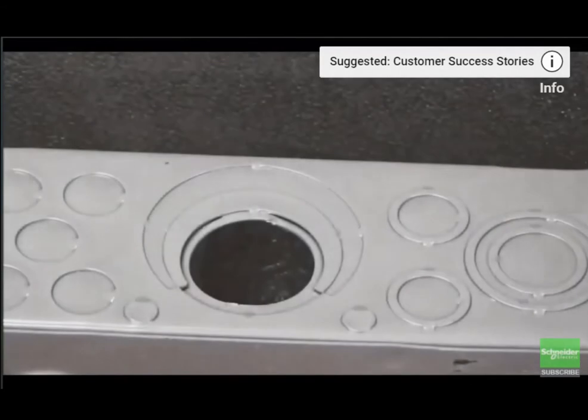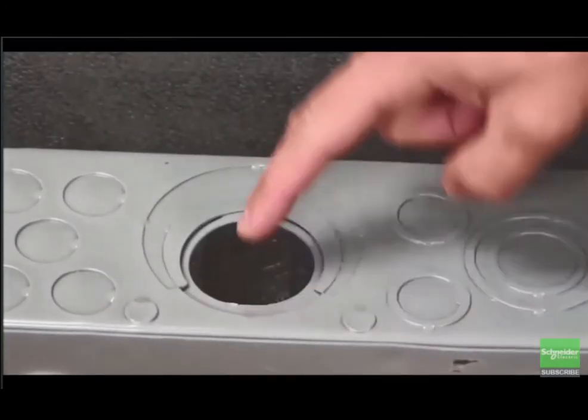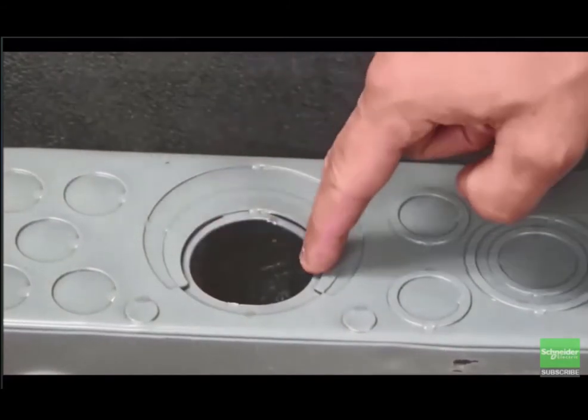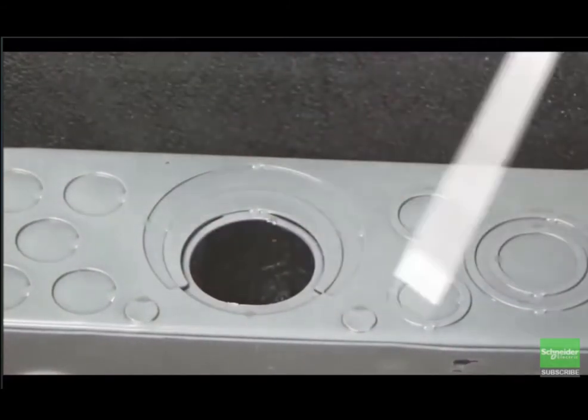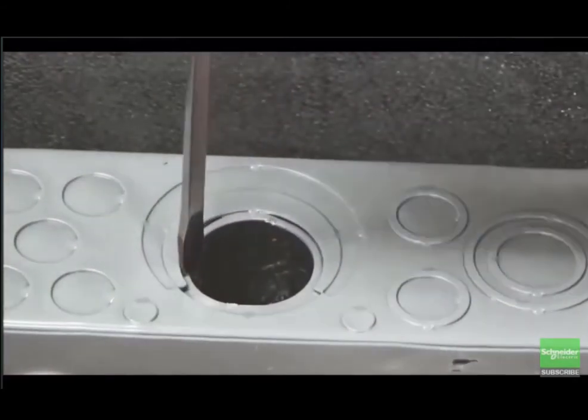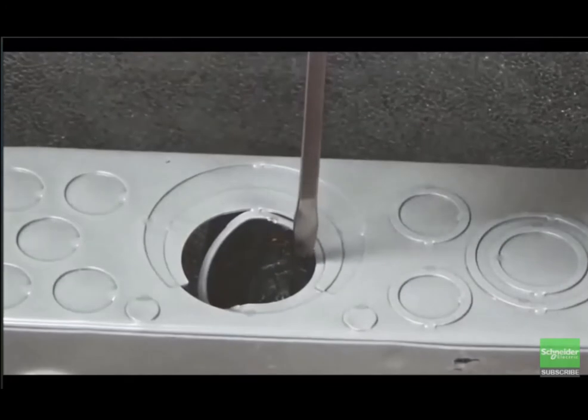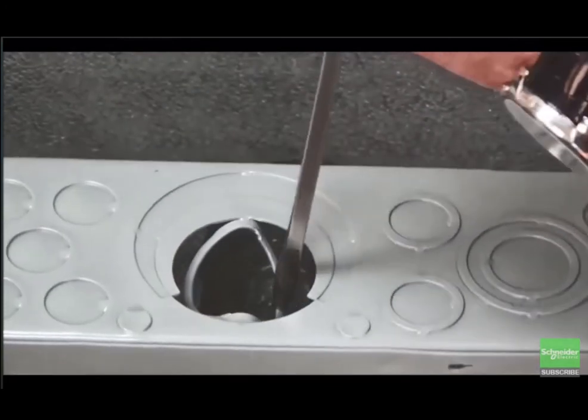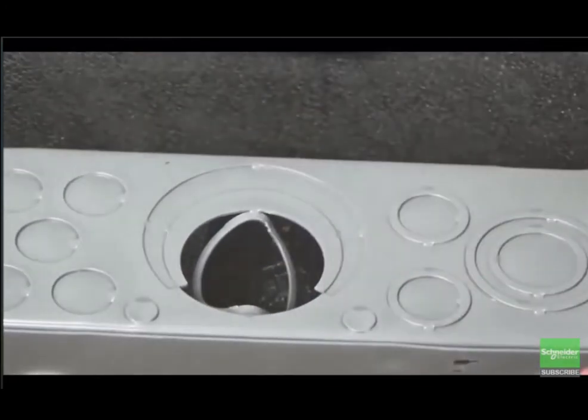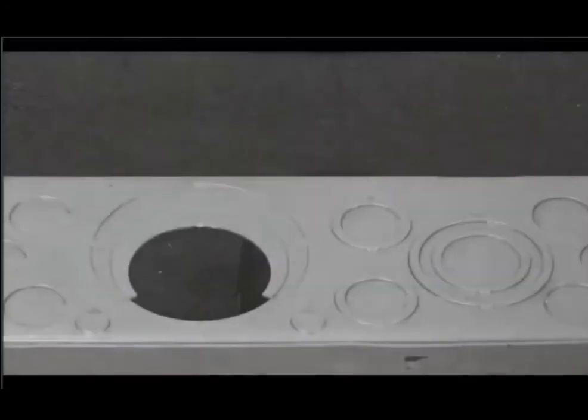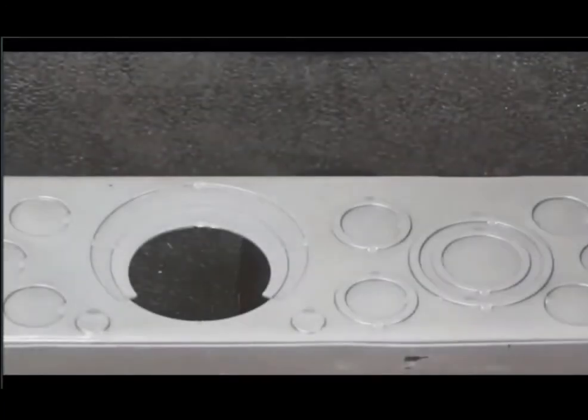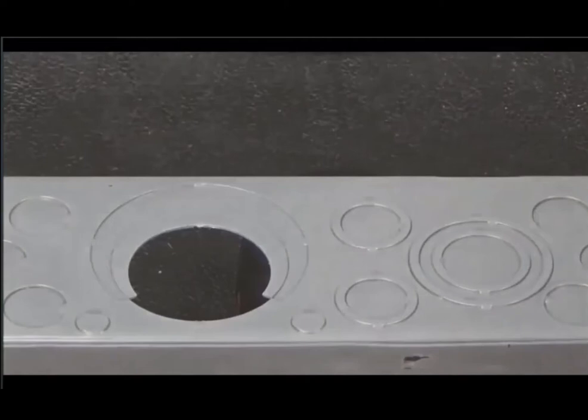So now with two of the knockouts removed, you've worked out to the next knockout. This one has two spot welds, so I'm going to go in between both of these to remove it. And this one is an actual knockout. And then it'll twist out. Now I've reached the size of knockout for my conduit that I was running, but if you did need a larger one, you would still work your way out until you reach an adequate size for your conduit.